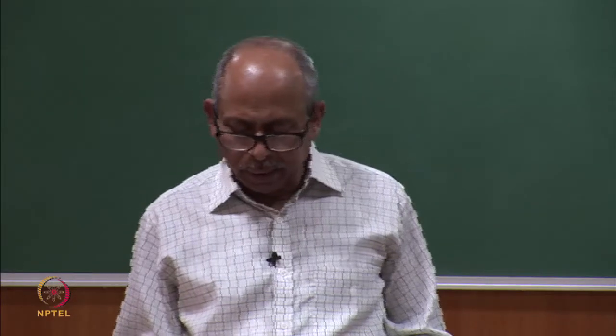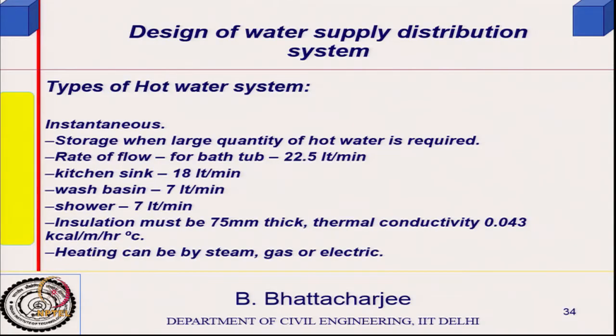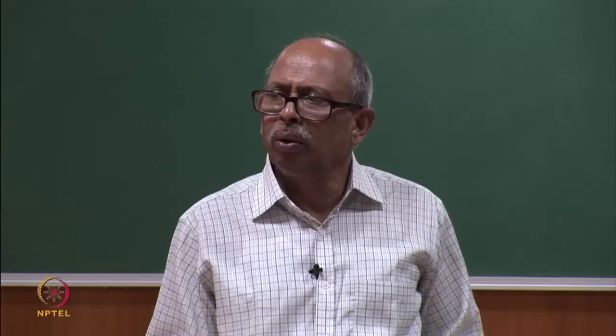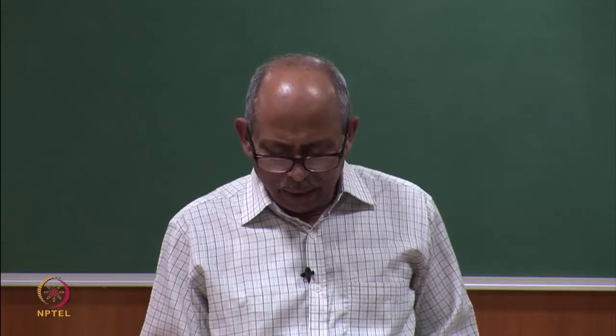We continue with the hot water supply system and the temperatures discussed earlier. Types of hot water supply systems include instantaneous systems. Storage is required when large quantities of hot water are desired. For a bath, the flow rate is around 22.5 liters per minute, for a kitchen sink 18 liters per minute, and for a wash basin — these values are given in the code. Insulation must meet thermal conductivity requirements also given in the code. Heating can be steam, gas, or electric; steam is almost gone, gas heating is very rare — it is largely electric now.